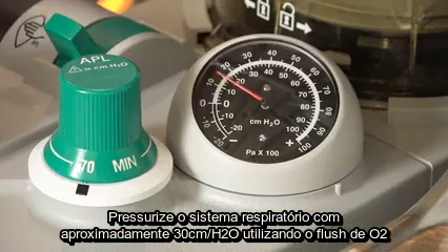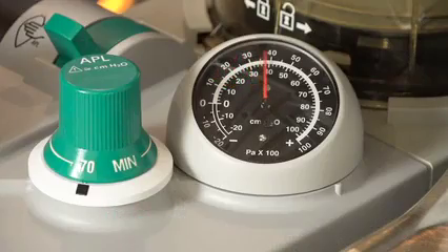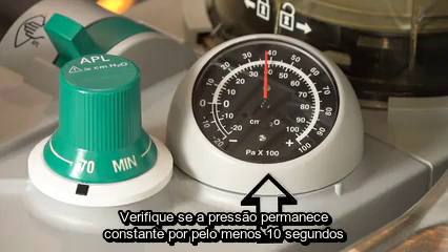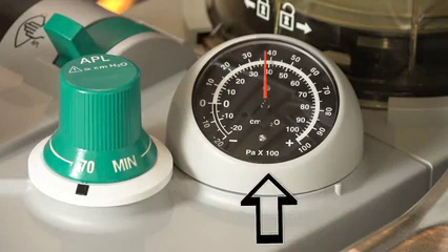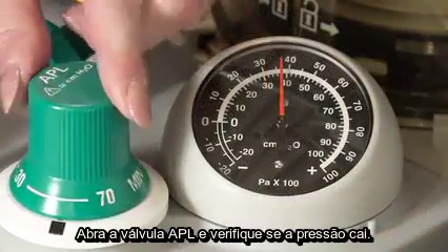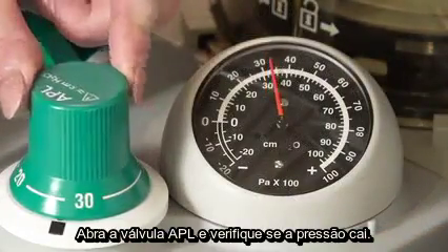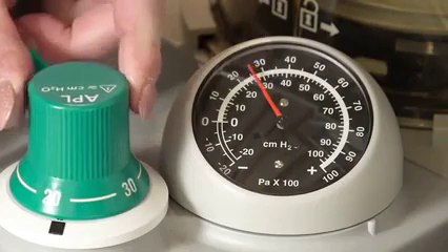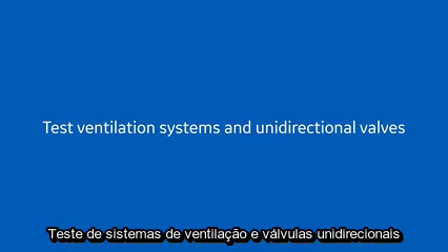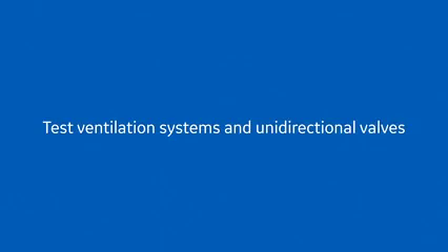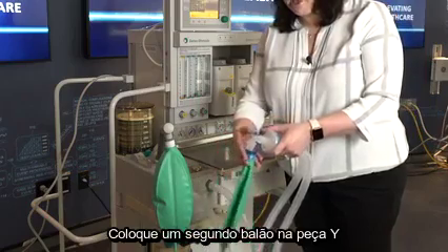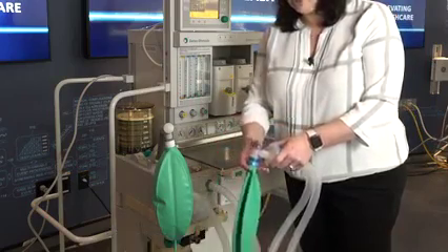Pressurize the breathing system to about 30 centimeters of water pressure with the O2 flush. Ensure that the pressure remains fixed for at least 10 seconds. Open the APL valve and ensure that the pressure decreases. Test ventilation systems and unidirectional valves. Place a second breathing bag on the Y piece.